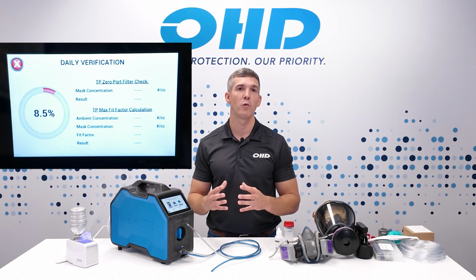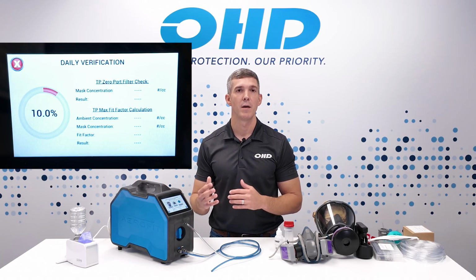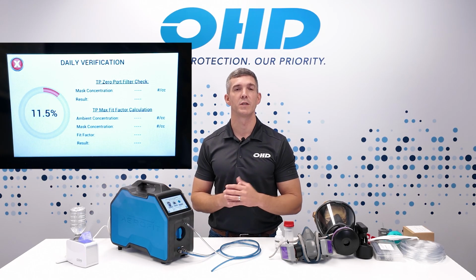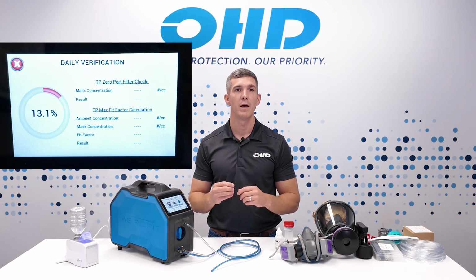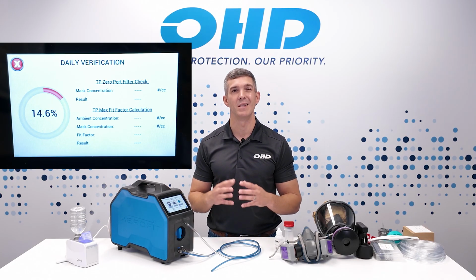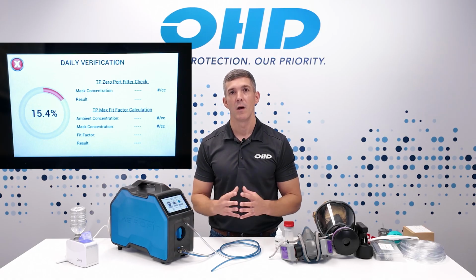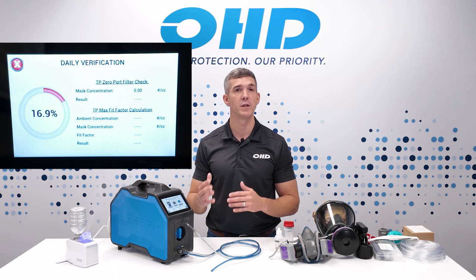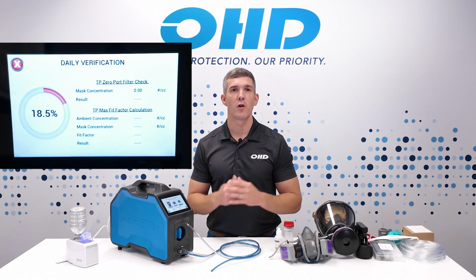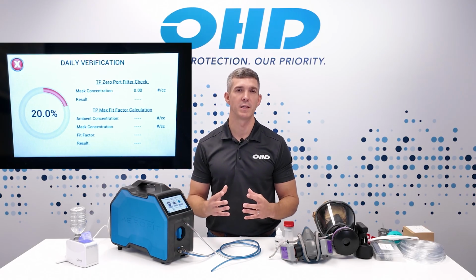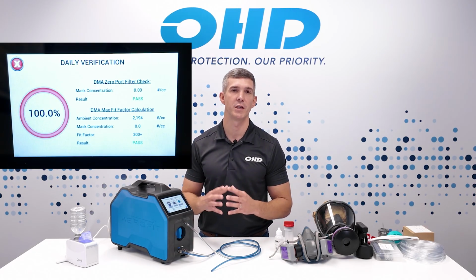If there is a failure, there will be guidance provided in the unit, but always ensure your clear tube is connected to the zero port well and that your ambient concentration is in a good range for testing. Also ensure the dual tube has no visible breaks or punctures. If there are multiple failures after troubleshooting attempts, please contact OHD tech support.